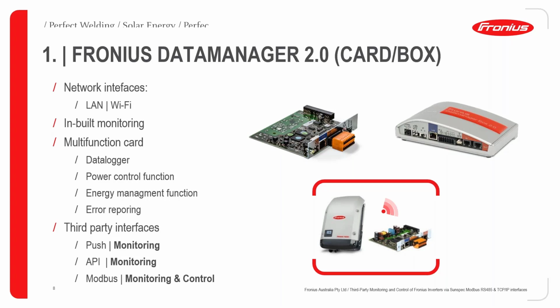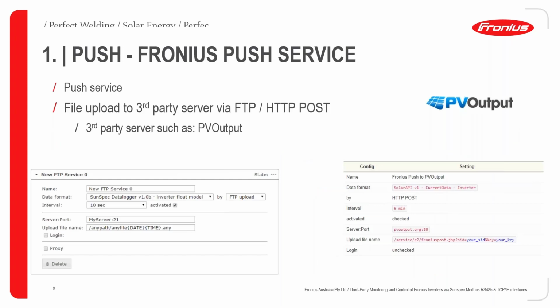It does enable, in a way, third-party integration with the Fronius solar system. That can be via push service, API, or Modbus. Key point is that push and APIs generally support only monitoring, and Modbus protocols can support monitoring and control. We'll go over this in a second, but it's a key point to point out.